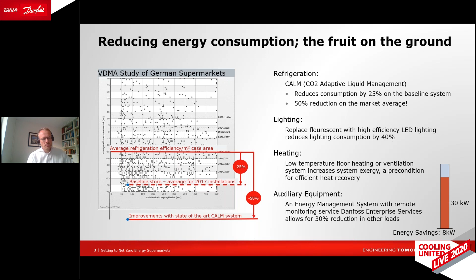And by the way, Kevin mentioned something interesting, and that was an efficient store. It uses about 400 kilowatt hours per square meter per year. That's pretty much where we are on the baseline store that we're talking about here, so it's very, very close. The next point is to reuse or recover the heat from the refrigeration system, and we can do that. We can cover the heating demand without even raising the discharge pressure or changing any settings on the refrigeration system per se. We should be able to cover about 30 to 50% of the heating demand.